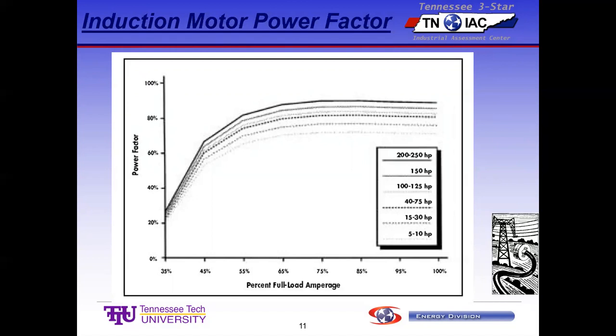And the other thing to note is that big motors have better power factors in general than small motors. So this big guy up here is what, 85 to 86%, something like that. The best this little guy can do is down here about 70%. That also has an impact. If I have a plant full of small motors, even if they're loaded, they're going to have a crappy power factor. So it's the summation of all of that at the meter. The summation of all that stuff going on in the plant behind it affects the power factor that the meter sees. Okay, so you've got a whole bunch of this going on.